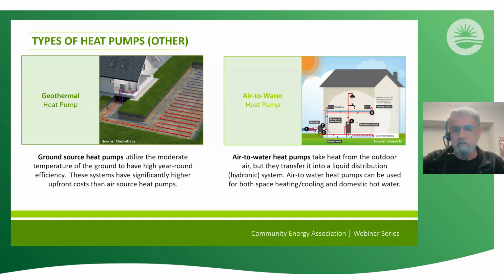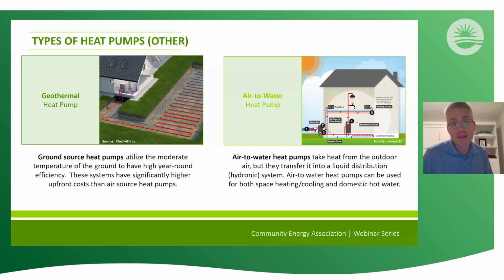And then the last technology that's becoming more available in our market compared to previous years is air to water heat pumps. This is for homes with hydronic systems, where it transfers the heat from the outdoor air into liquid distribution, so water. And this can be used both for space heating and cooling, as well as domestic hot water, or all three applications at once.